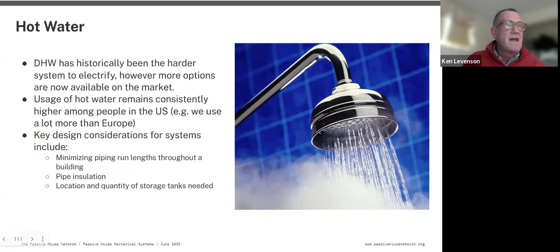The big thing we go back to again and again, like a mantra, is minimizing piping runs and insulating them well. We do not want the heat going out of your shower head to be heating up the whole house all year round, 24/7—that's problematic. Reducing use is largely dependent on occupants, but the system layout can make a big difference. Some obvious things: low flow devices, smaller diameter pipes.